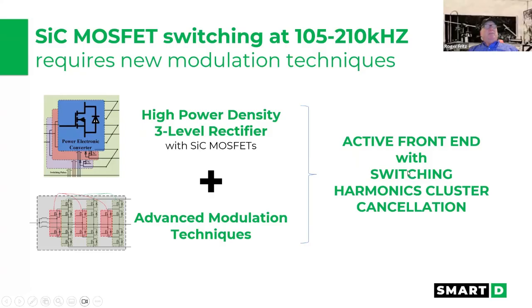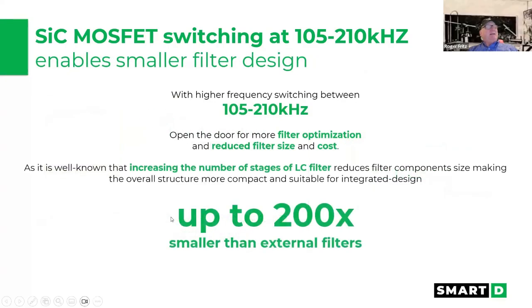Well, when that motor becomes basically feeding power back, it's got to be taken somewhere. You can't have that excess power. So they have typically on a standard VFD been dumping it off to resistors. So you'll hear a lot of these resistor banks added to VFDs in cyclical applications to eliminate voltage spikes. And we've also created multi-level outputs on this. So we're not just one switching device, we're multiple, so we can stage it. So at high speeds, we can create that power waveform with high frequencies, 105 to 210 kilohertz, where everybody else is between 1.5 and roughly 10 kilohertz. So that's where all those jags are coming from.